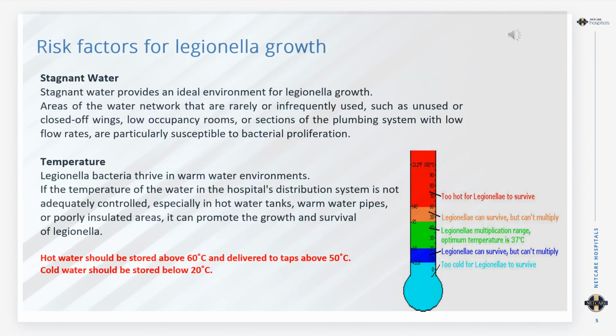We're now going to look at some of the risk factors for Legionella growth. The first one is stagnant water, which provides an ideal environment for Legionella growth. Areas of the water network that are rarely or infrequently used, such as unused or closed-off wings, low occupancy rooms, or sections of the plumbing system with low flow rates, are particularly susceptible to bacterial proliferation.